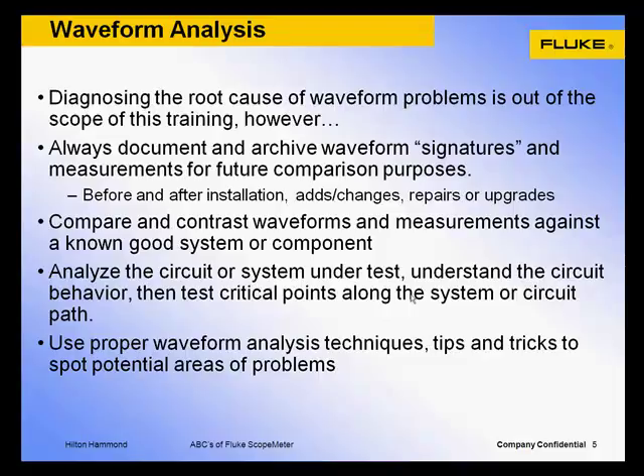Capture and document waveforms before and after a successful installation, repair, or even an upgrade. Documenting both the good and bad waveforms may provide clues to problems you may encounter in the future. Or if you don't have that history, go to a system that is working and compare waveforms between the good and bad system, looking for any differences. Use the following waveform analysis techniques, tips and tricks to spot potential areas of problems.